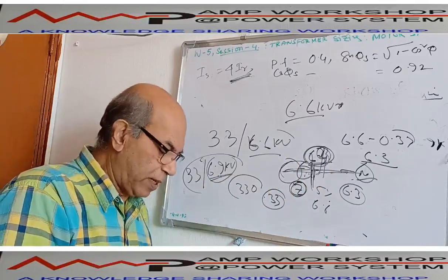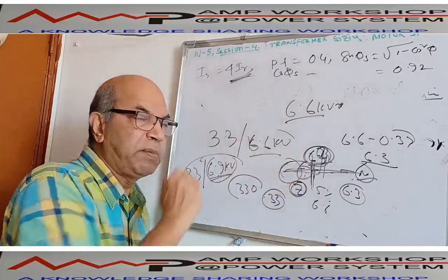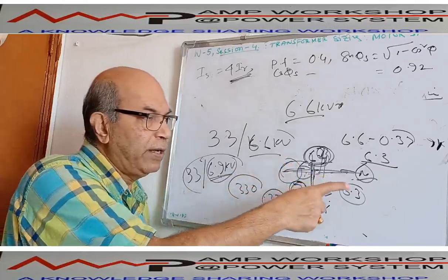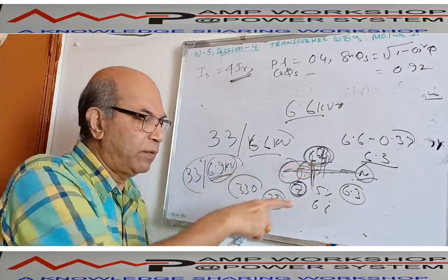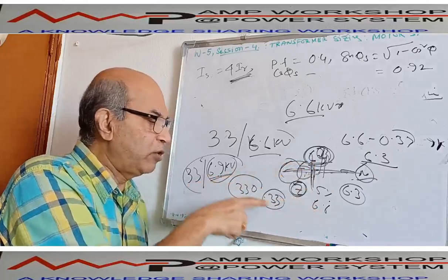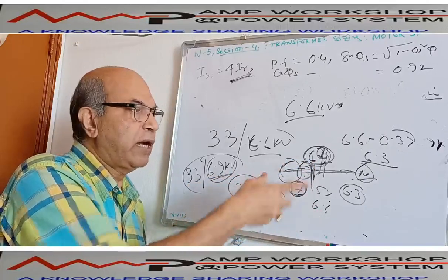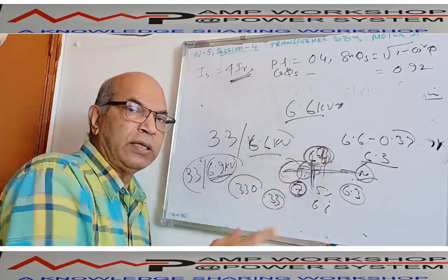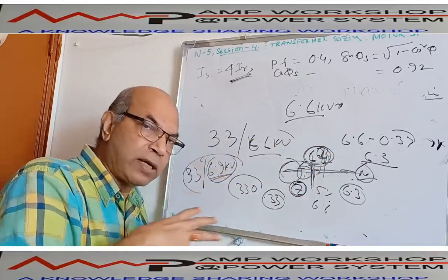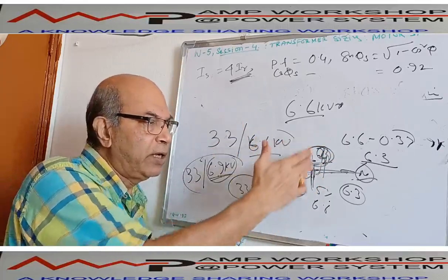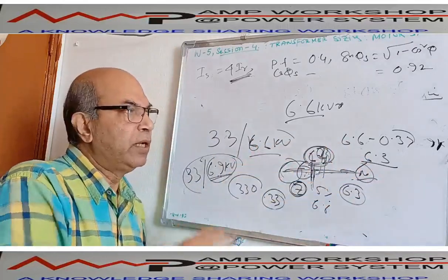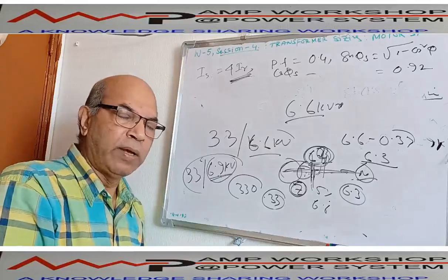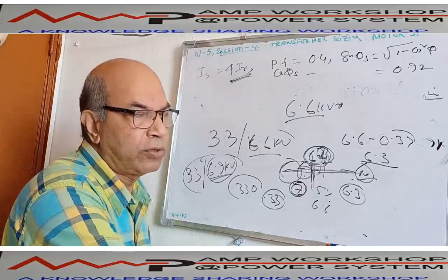Or if we feel the transformer will not be in normal running condition, it will be 50% loaded, then we can define this no load voltage with the 50% drop, not 100% drop. So in that case, instead of 660 volt, it will go half of this. So that will add with the rated condition, that voltage drop will be considered during running. So in the running condition, we'll get 6.6 kV. During motor starting, the rest of the voltage drop will be allowed. In this way, we can calculate the voltage drop and that will give the transformer voltage drop calculation.